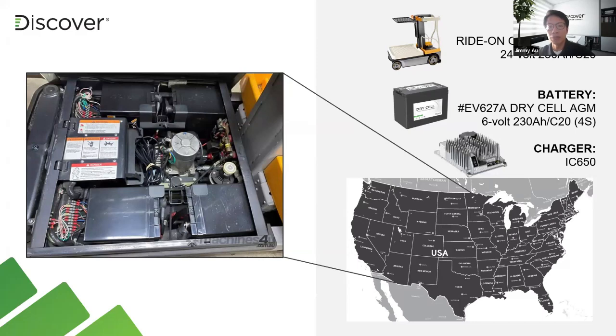With an AGM or gel battery, because it's fully sealed, you will not be able to reverse the effects. So having temperature compensation and the proper charging algorithm is critical to get the longevity the batteries are designed for.